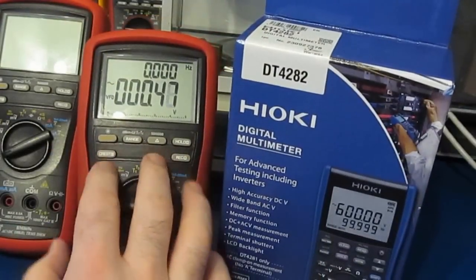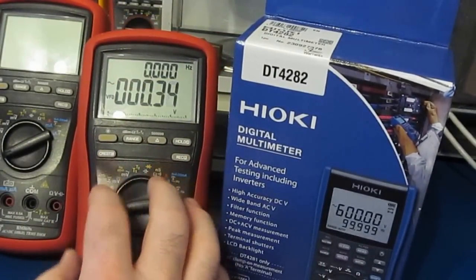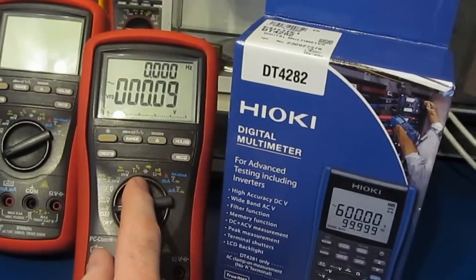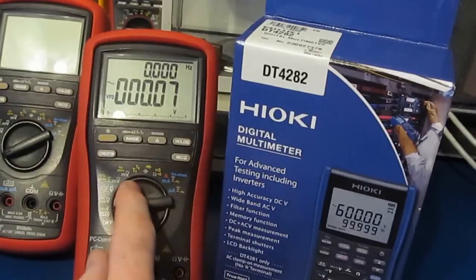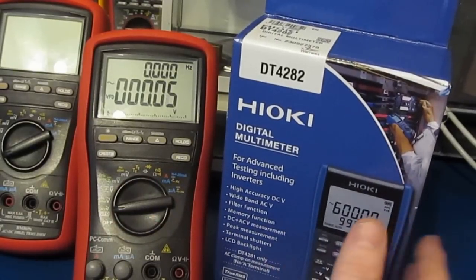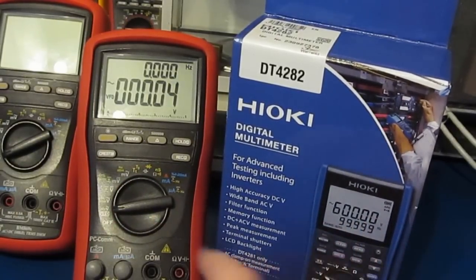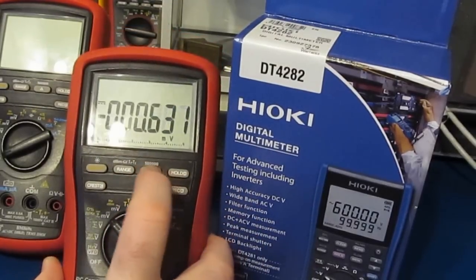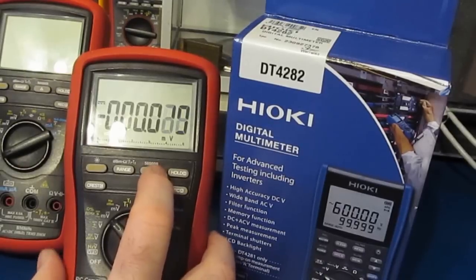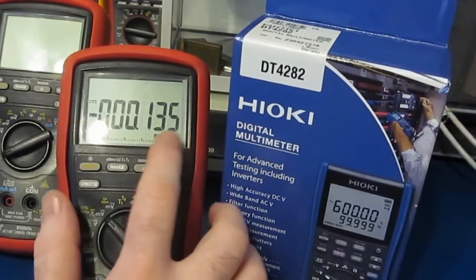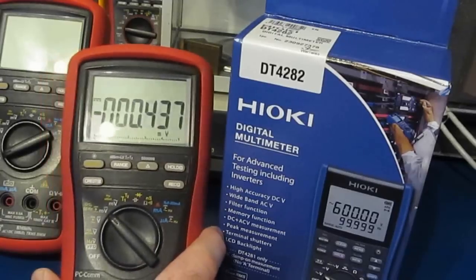One thing I was interested in is the lowest operating voltage range. The Brymen has a 500 millivolt range, while the Hioki has a 60 millivolt range. But keep in mind, in that 500 millivolt range, this meter also allows a 500,000 count mode, so we can get all the way down to 1 microvolt resolution.